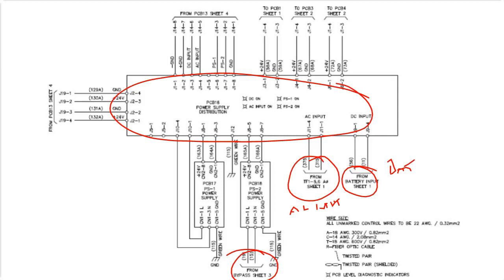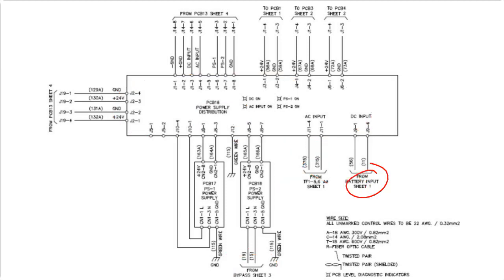Okay. They all go onto this power supply distribution board. And 2 of these can fail, and the system will run. As long as you have one of these, either that one, or this one, the system will operate as normal. Okay, so we have triple redundancy built into our power supplies. And then all the power supplies go out to our boards using these terminals. Yeah. Okay.